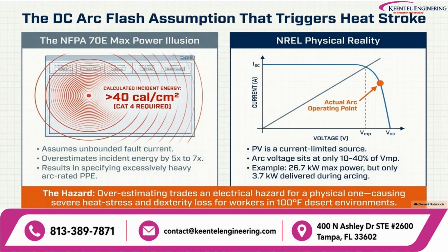Oversimplifying DC arc flash calculations creates a severe, unmanaged safety hazard. Standard maximum power assumptions treat the DC array as an unbounded power source, calculating incident energies exceeding 40 calories per centimeter squared, and mandating Category 4 blast suits. However, physics-based NREL research shows solar arrays are strictly current-limited sources, operating at arc voltages between 10% and 40% of VMP. In practice, a theoretical 26.7 kilowatt fault only delivers around 3.7 kilowatts of arc energy. Forcing technicians into heavy, multi-layer suits in triple-digit desert heat trades an exaggerated electrical hazard for very real, acute heat exhaustion.